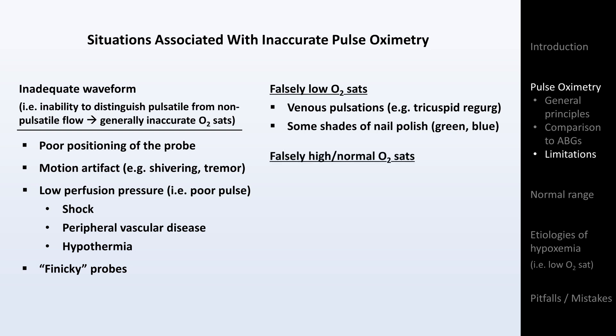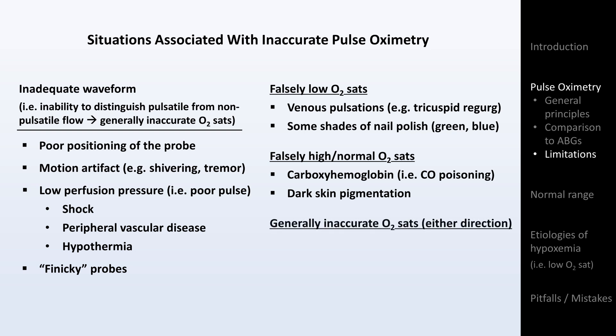Causes of falsely high or falsely normal O2 sats include the presence of carboxyhemoglobin, as seen in carbon monoxide poisoning, and dark skin pigmentation. Causes of generally inaccurate O2 sats — meaning they can be either falsely high or falsely low — include the presence of methemoglobin, which is a rare but serious side effect of some medications, and ironically, hypoxemia itself. That's right: the lower the O2 sat is, the less accurate the reading.